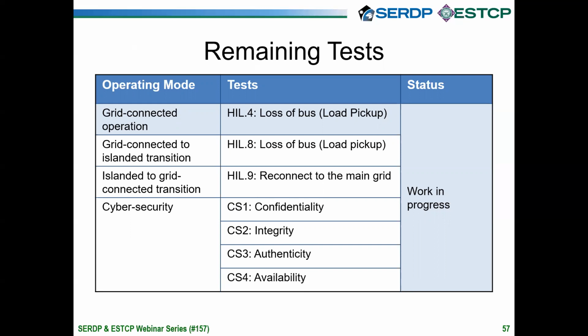When we are reconnecting, the algorithms regulate first the voltage, then the frequency, and finally the phase, so that the microgrid starts tracking the main grid. And after these 3 stages, it is able to connect with the relays to the feeders and work together with the main grid. The project also has some tests that we still need to perform for cybersecurity capabilities. These are the classical confidentiality, integrity, authenticity, and availability tests. As I said, the platform has software support for this, but we need to test this in the context of the actual power grid application.